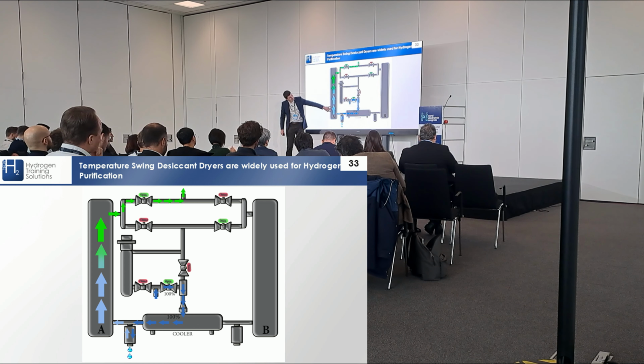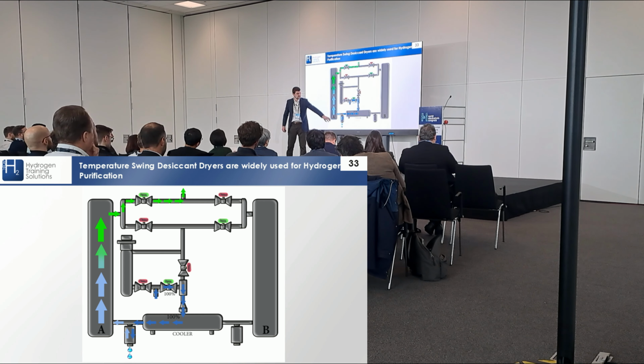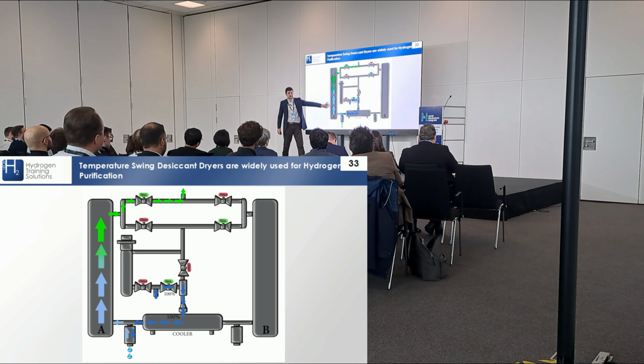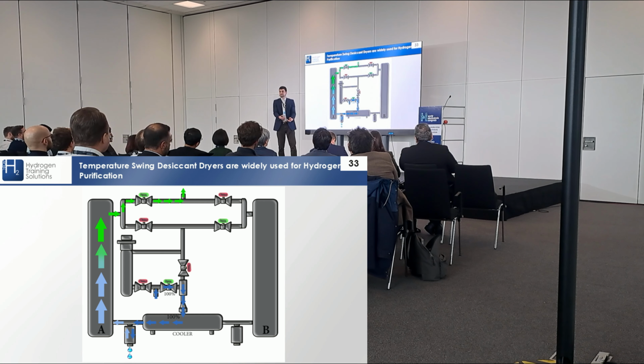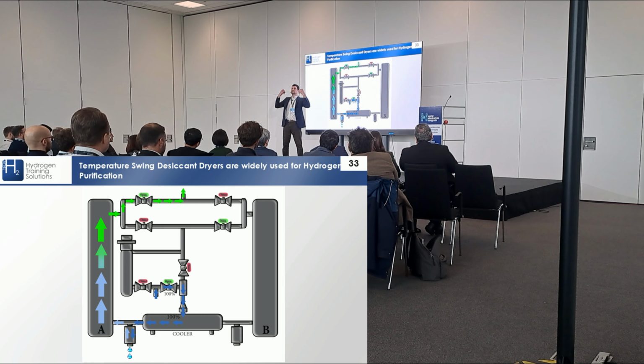The hydrogen is still saturated, but the dew point is only about 10 or 15 degrees Celsius. The gas will go into this vessel, and when this vessel is relatively cool, i.e. 10 or 15 degrees Celsius, the desiccant will take in all the water.